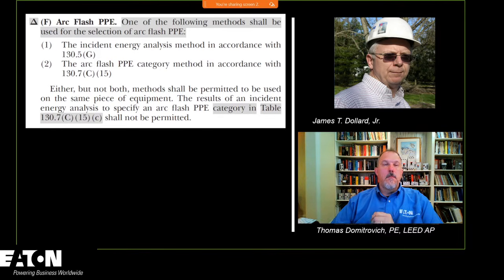When you're in the tables and you're in an equipment category and your arc flash PPE category 2, we're going to tell you need to wear 8 calories in that arc flash PPE category 2. I can tell you that in that arc flash PPE category 2, for example, you're in a panel board, 480, 277, 200 amp, 400 amp molded case circuit breaker, there is no way you're getting anywhere near 8. You're going to be under 2 calories. The tables are primarily conservative. And here's the problem. Now I'm an engineer and I run an analysis and I come up with 7.5. Now I'm putting you in an 8. I'm going to say arc flash PPE category 2.